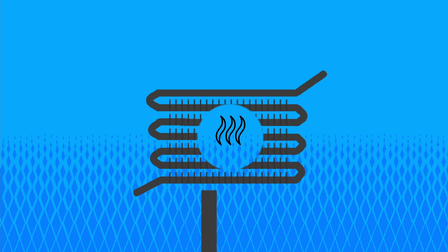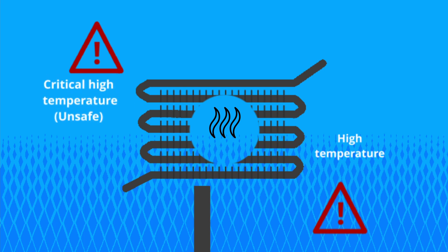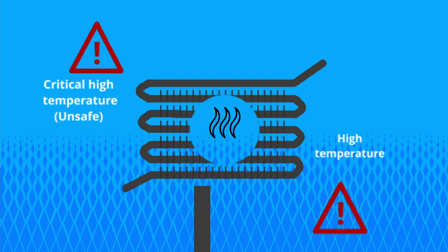If serving as a condenser sensor, it will enable two new configurable alarms: one indicating elevated temperatures due to dirty filters or an obstruction, and another indicating critical high temperatures when unsafe equipment operation is reached, disabling the control outputs.